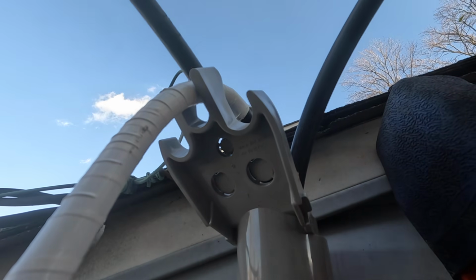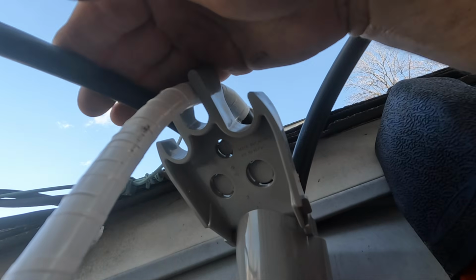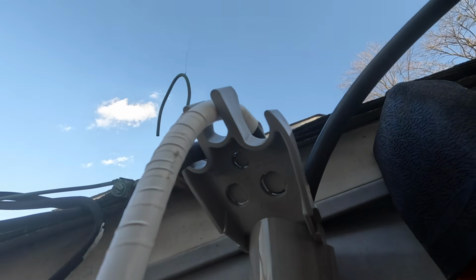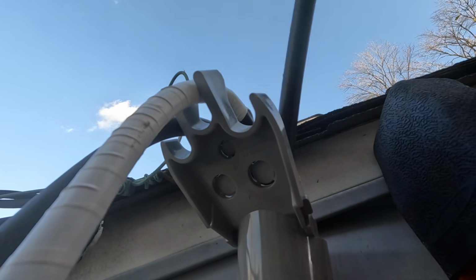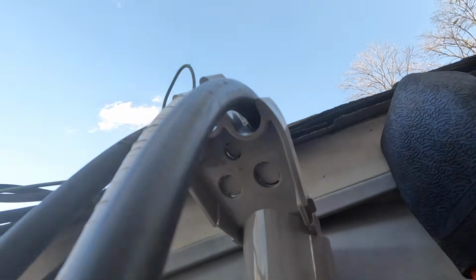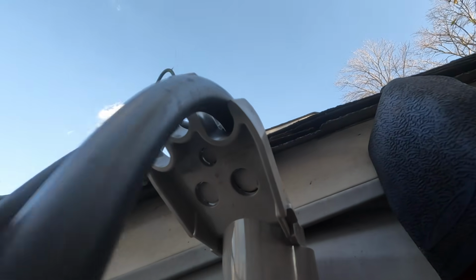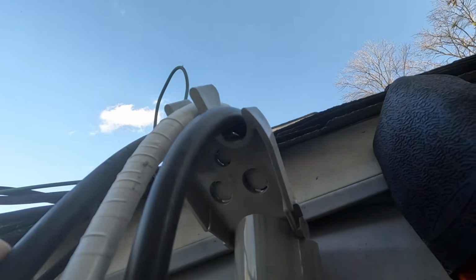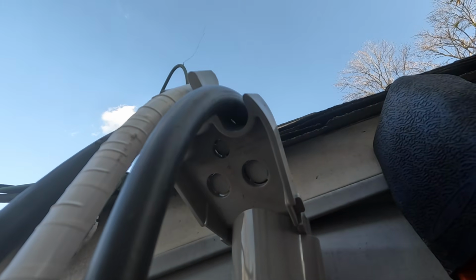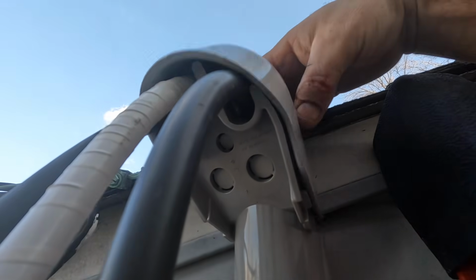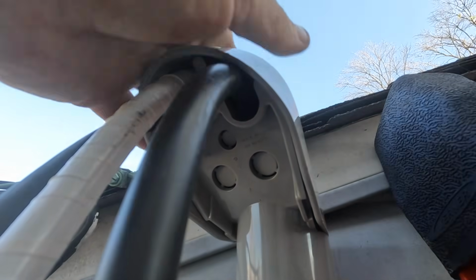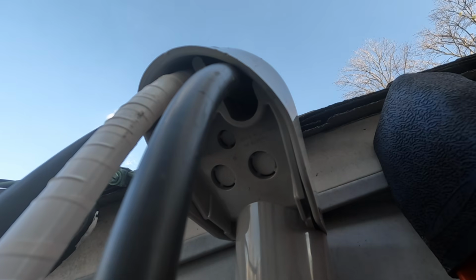So here I'm just folding over my service entrance conductors so that I can get the cap of the service head back on. And you need to make sure that the conduit's a couple inches away from the finished surface on the side of the house here in order to do that, because you won't be able to get the back side on. Then they clip on either side and it's on.